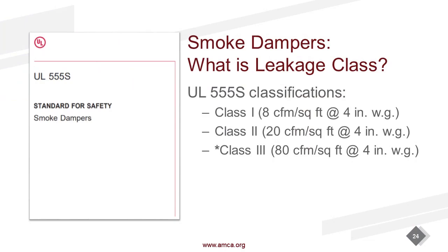But you can see what the leakage ratings are: 80 CFM per square foot at Class 3. Then we jump to a Class 2, it's 4 times tighter. It seals that much better. It's 20 CFM leakage per square foot. And then our Class 1, 8 CFM. That's a tight, low leakage damper. Now don't get this confused with AMCA leakage certifications like Class 1A, Class 1. Those are for control dampers and other volume control applications, not life safety dampers.